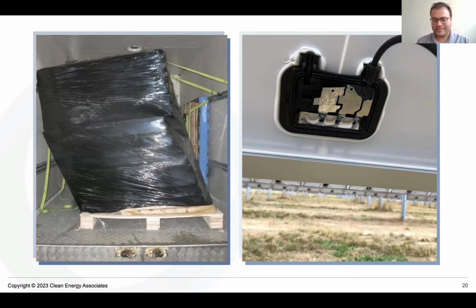Multiple PV modules are connected to each other in a string, and the string goes into the inverter. We have around 1500 volts applied, and there is a current of 10 to 11 amperes flowing. Just imagine the site is operating and this module lid comes off. This is going to be the cause for a major thermal event.